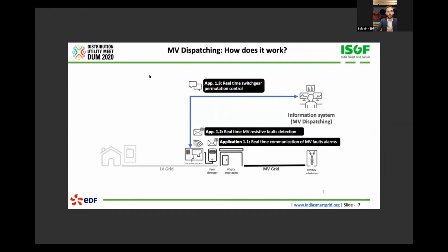So here we're talking about the medium voltage dispatch. The essential component here is the data concentrator. We use the data concentrator of the AMI solution to collect and transfer network information, like the fault detector, which informs where a fault is on the medium voltage, and transfers it not only to the AMI system but also to the SCADA system and to the information system of the MV dispatch.